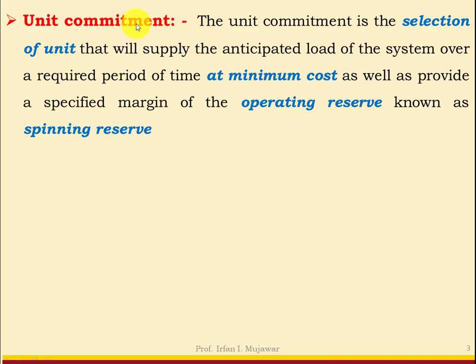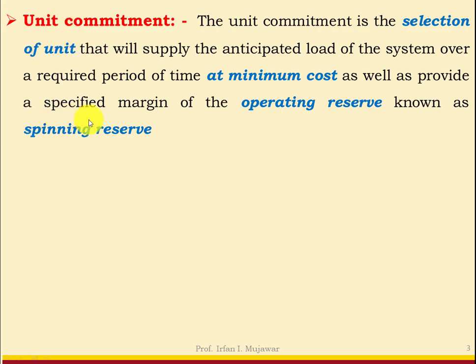The unit commitment is the selection of units that will supply the anticipated load of the system over a required period of time at minimum cost, as well as provide a specified margin of operating reserve known as spinning reserve. Power plants always have an operating reserve — for example, if rated capacity is 100 MW, we may keep 10 MW extra for sudden peak loads. That 10 MW is the operating or spinning reserve.